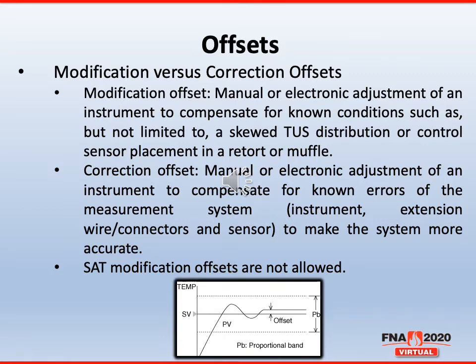Whereas a correction offset, again, is a manual or electronic adjustment of an instrument to compensate for known errors in a measurement system, to make the system more accurate. So the correction offset is bringing the instrument back to a nominal. For instance, you're doing a calibration of a process controller and it reads 2 degrees off and you want it to be accurate. You would go in and possibly use the offset or bias or input shift, different trade names for different instrument manufacturers, and use that electronic offset to bring it back to the nominal temperature.